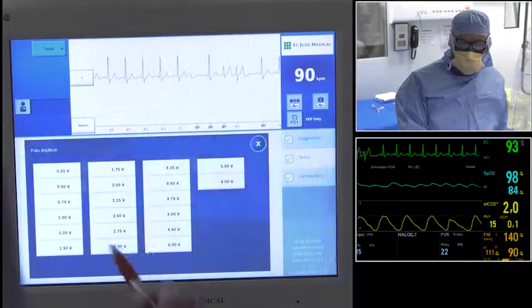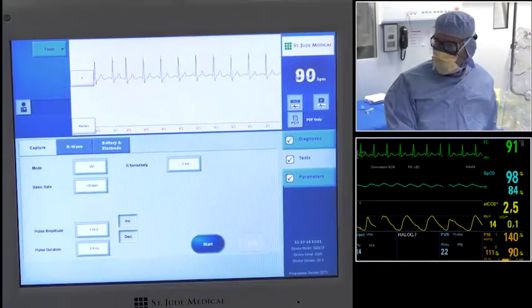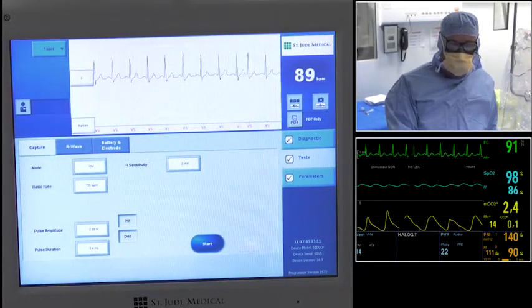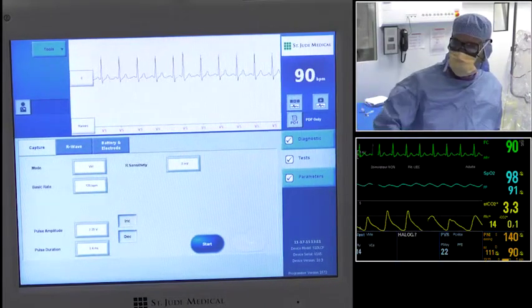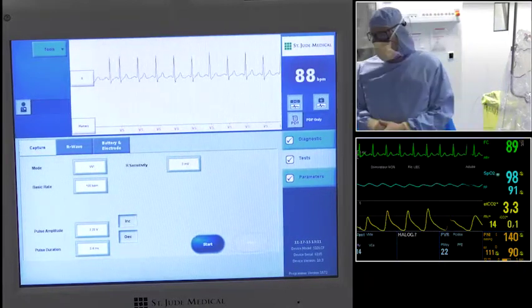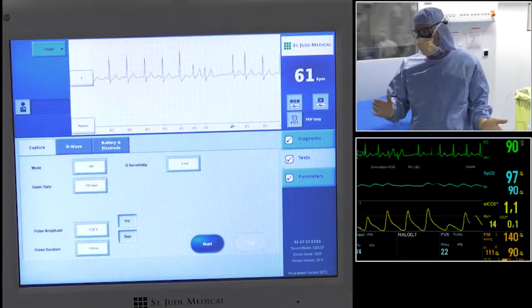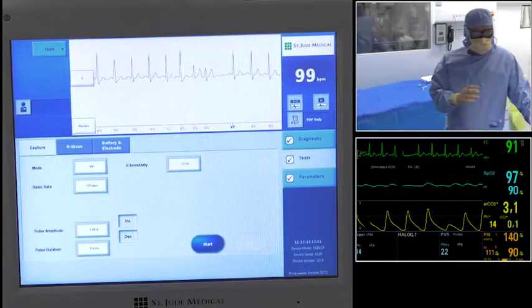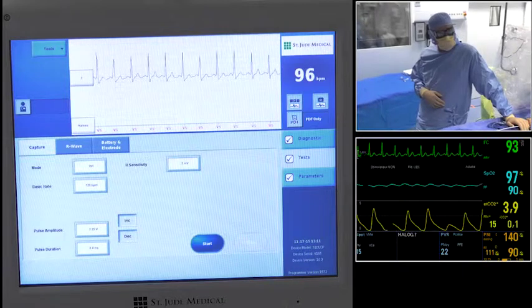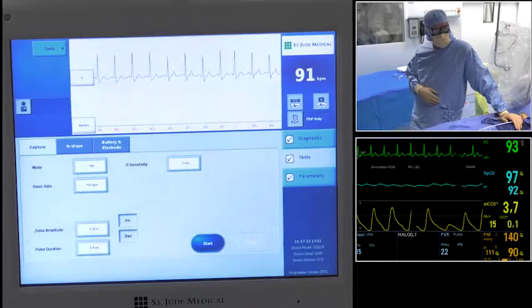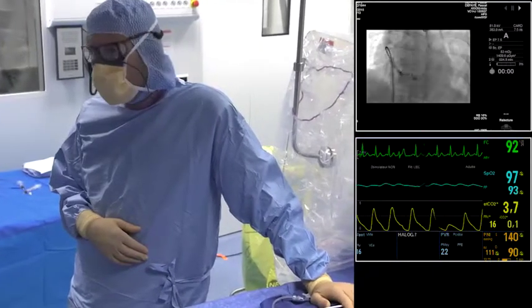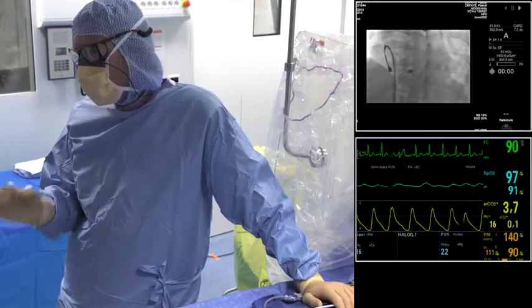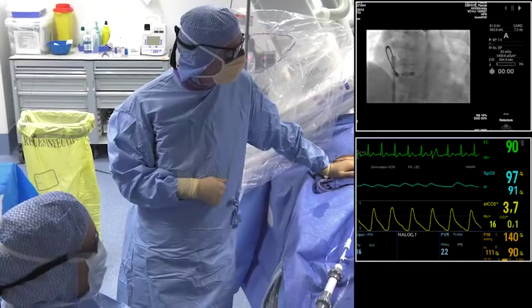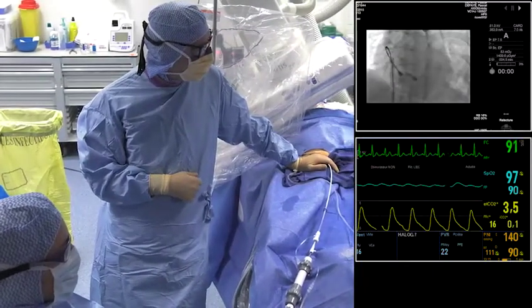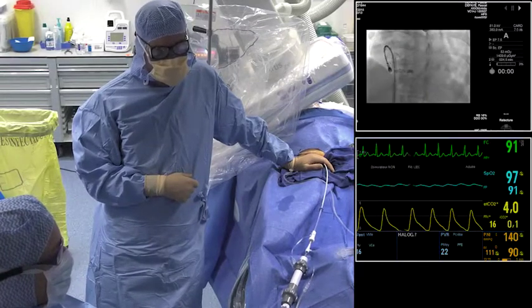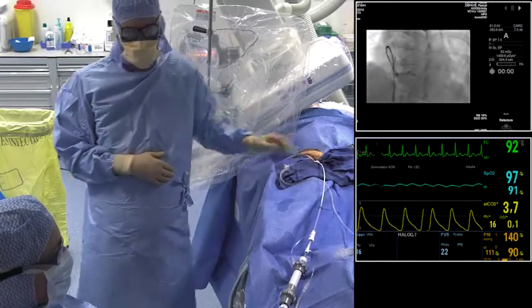So for the moment, we are in the acute phase. The threshold is 2.5 volt, but we are relatively sure that we are screwed because the impedance decreases and the sensing decreases relatively, from 9 to 7.5. And the threshold is 2.5. We will wait, and I think it's very important to have only one position and to not reposition the nanostim. If we wait, sometimes we wait half an hour, we will do some tests at 5 minutes, 10 minutes, 15 minutes, and if there is a decrease of the threshold, we are sure that the leadless is well screwed. And we are relatively sure that tomorrow or in half an hour, the threshold will be excellent, less than 0.5 volt.